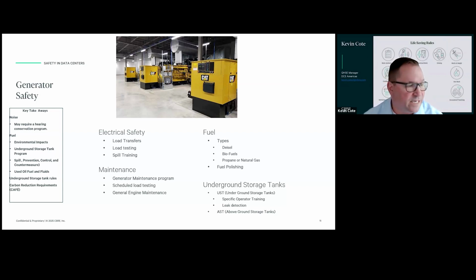Generally in the US, they identify an A, a B, and a C operator. An A operator is generally the owner. A B operator is either the on-site person or a contractor that comes in and manages that program. So they're identifying what kind of system you have, how you test, how you have your leak detection, your annual type of stuff. And then you have your C operator. Your C operator is generally the day-to-day person. They're going to take readings on the tank. They're going to walk around, make sure there's nothing in the sumps, make sure there are no obvious signs of leaks for those systems.